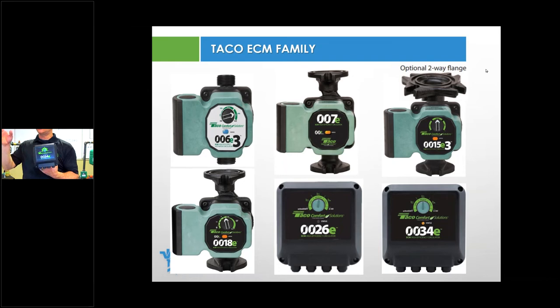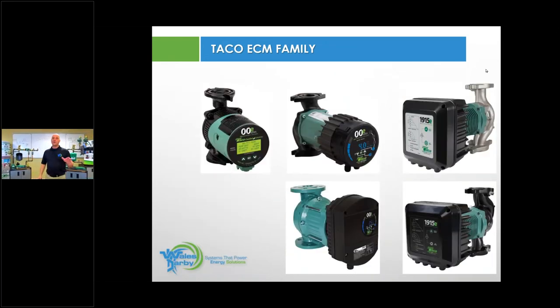We have the 0026 and the 0034 in cast iron and stainless. So you're just seeing a part of what Taco is doing. We're the only game in town with the one there that says 00E all the way to the left. That is a temperature driven circulator. That circulator will look at the supply temperature and the return temperature. And if we set that for 20, because that's what our boiler wants, that's what our system wants, that circulator will try and maintain that 20 degree delta T every single time it's on. So we're the only game in town with a delta T circulator.